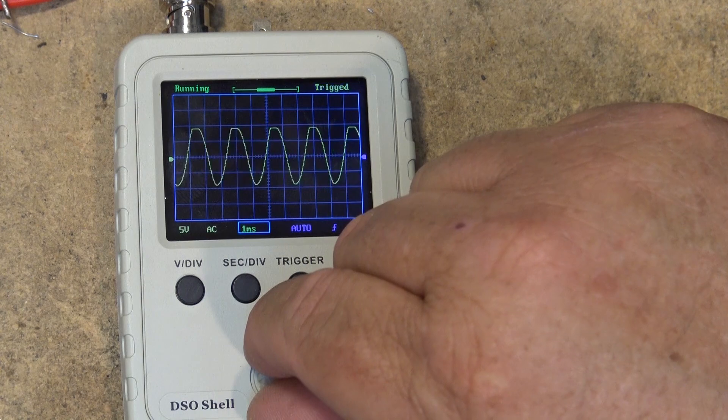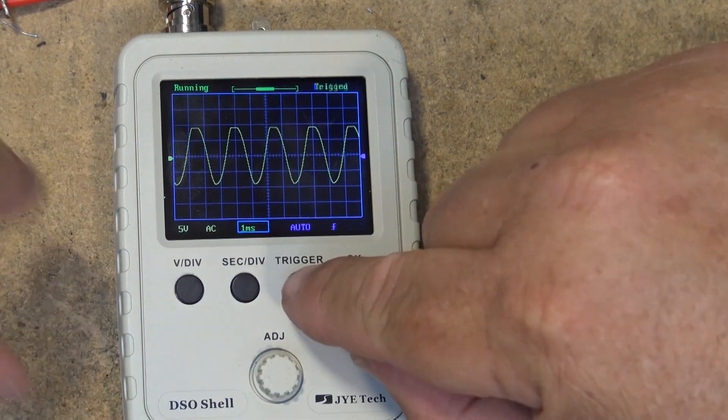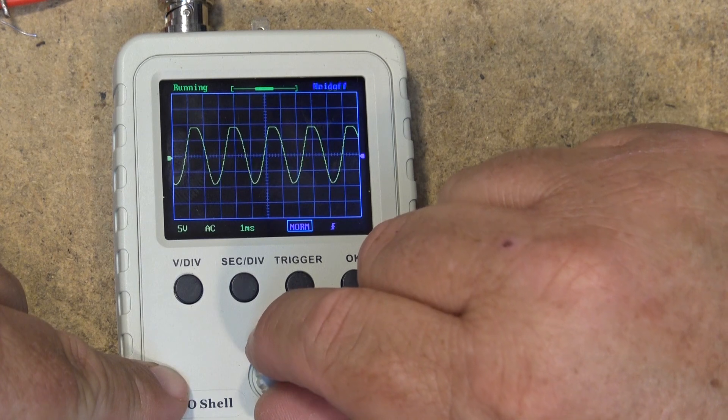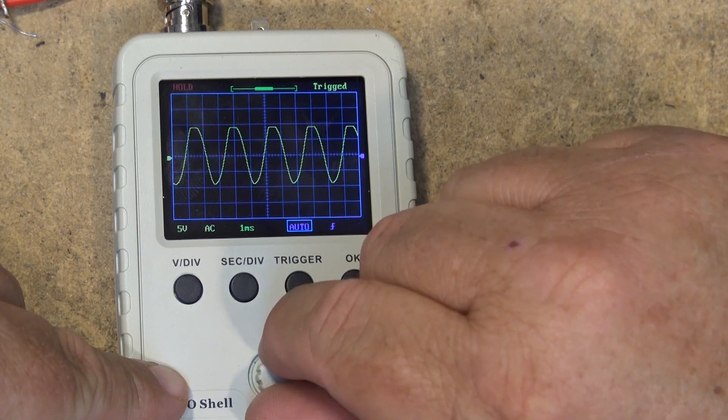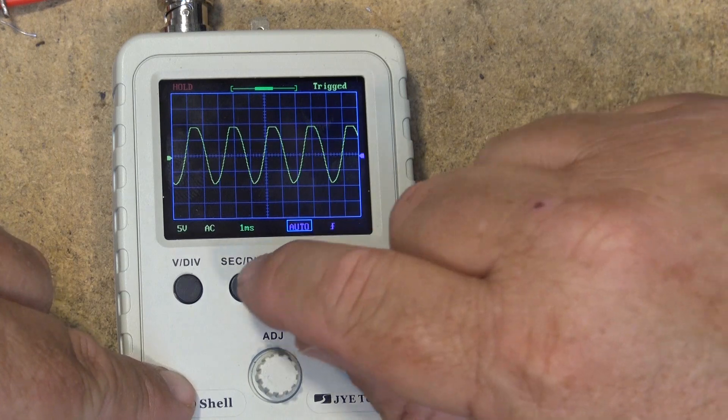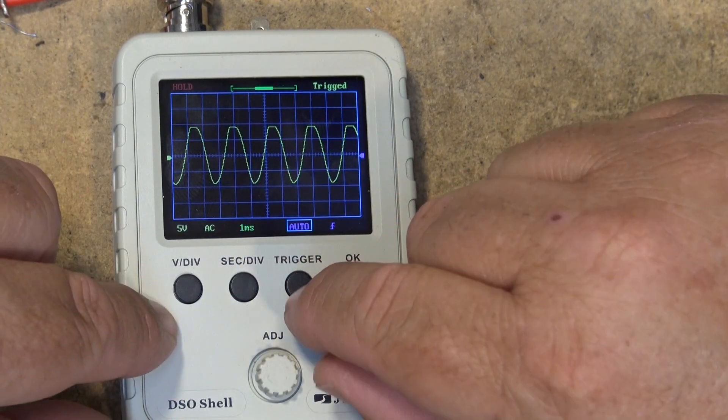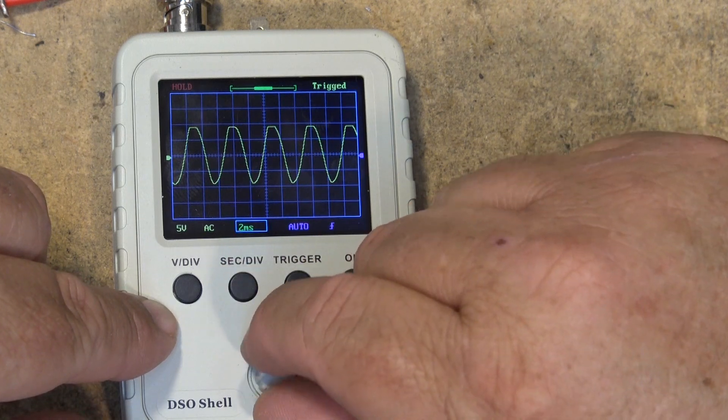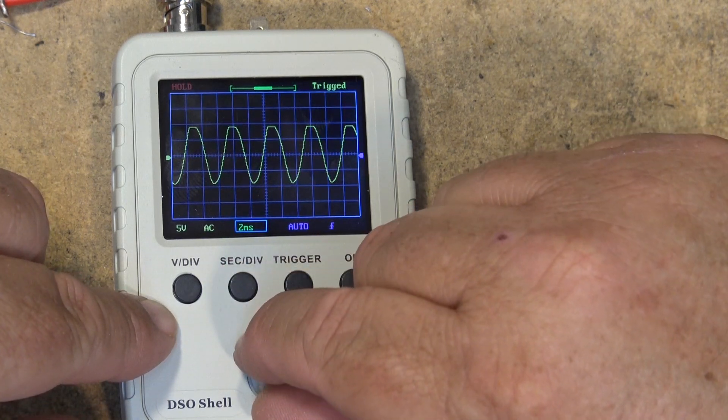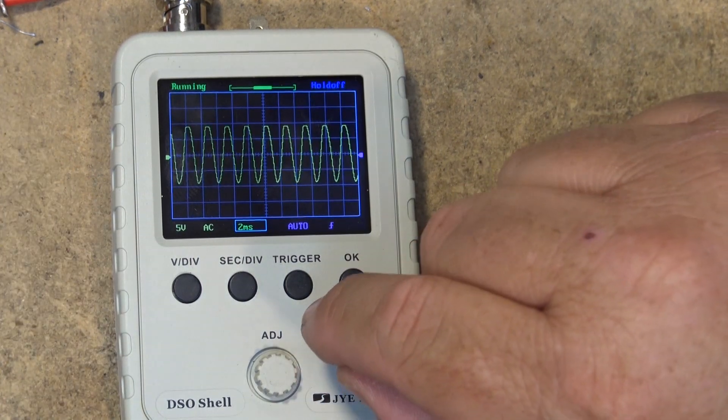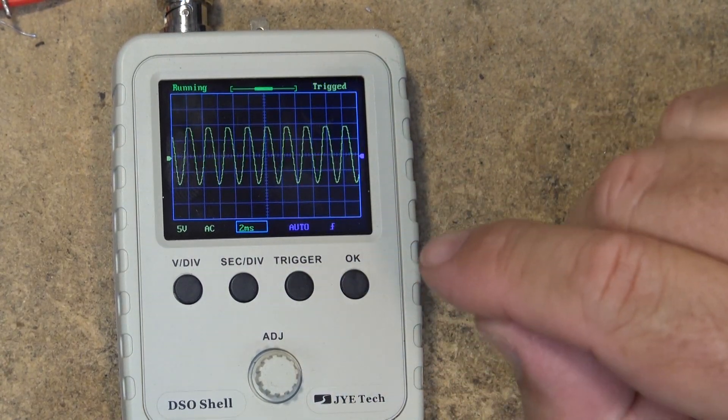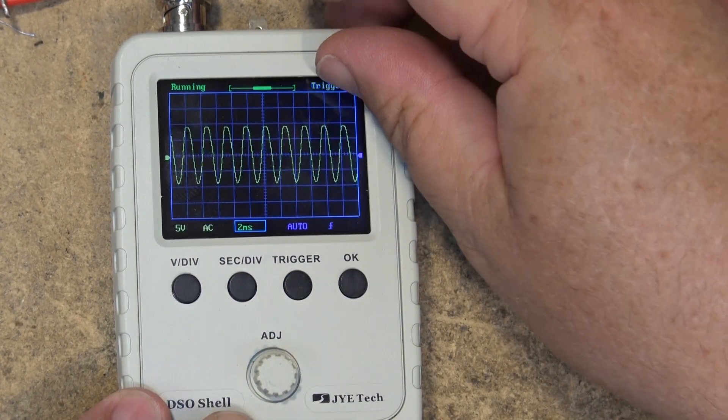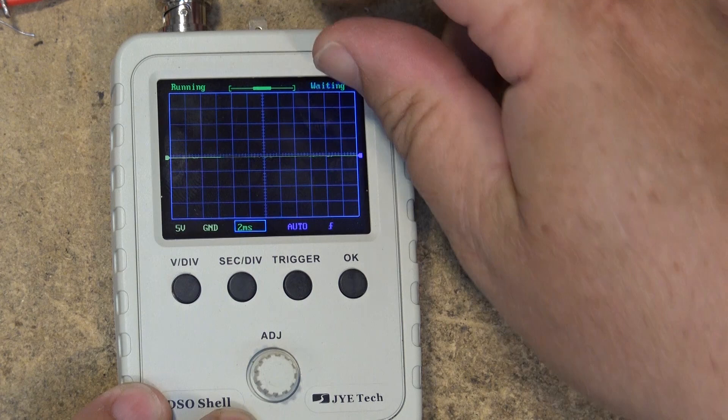For trigger I can set it to auto, normal, or single. I'm in hold mode now. To adjust my vertical position, if I set my input to ground and press and hold the V division button for three seconds, this will center the display.